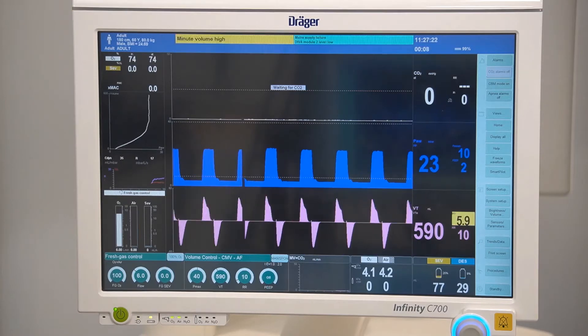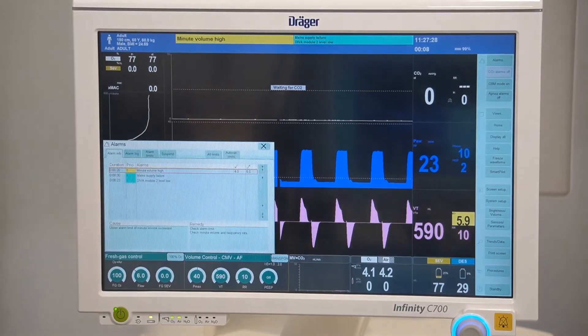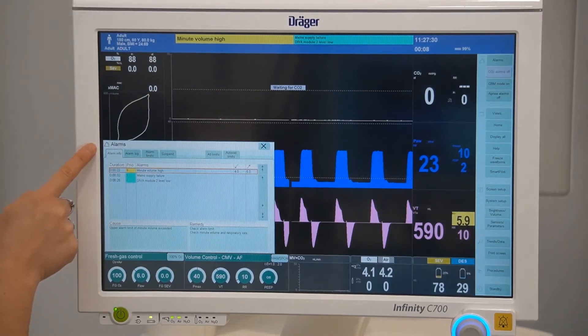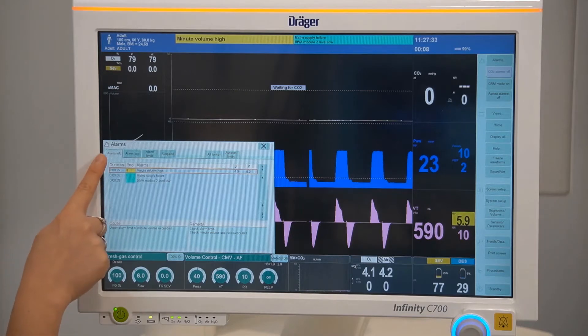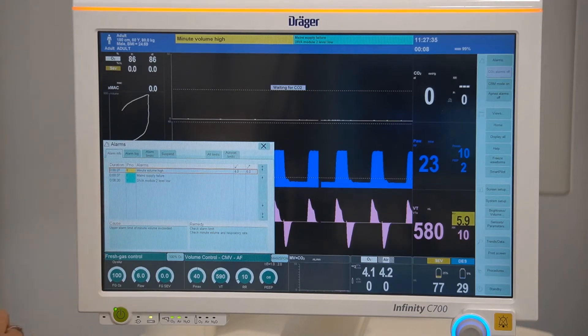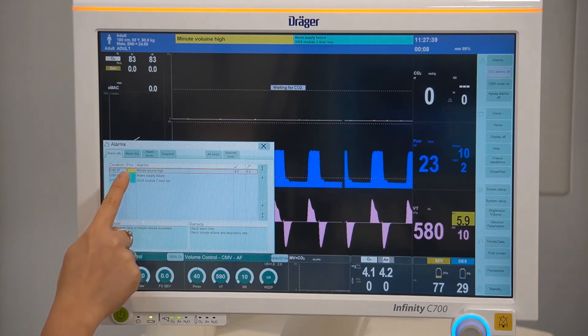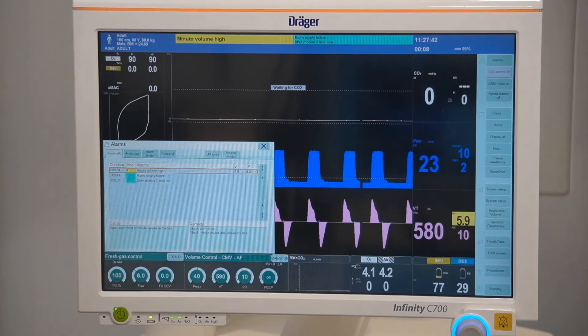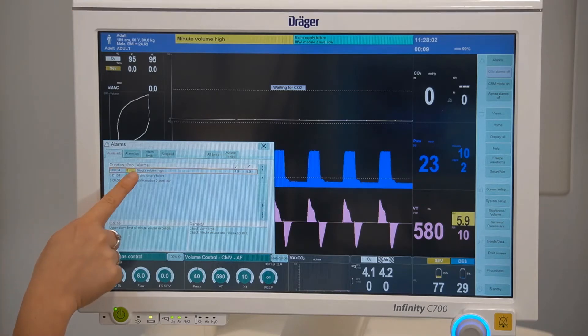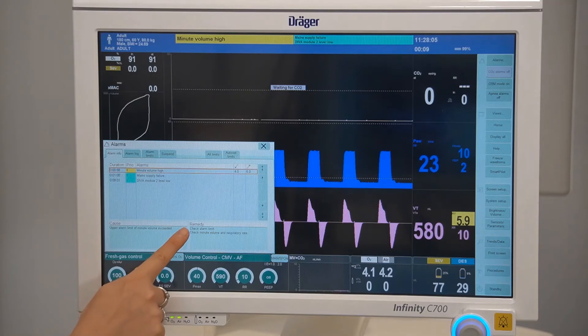To access more information regarding an alarm, you can do this by tapping on the message in the header bar, which will display the alarm dialogue window. Here it will open up to alarm info, where it will display the duration of the alarm, the priority, and the specific alarm message. The highlighted alarm message will also display the specific cause and remedy.